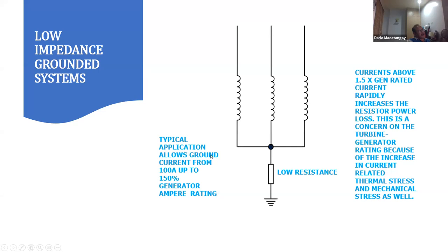What they do is sometimes they will design the ground current to be about 100 amps to about 150% of the generator ampere rating. So you allow 100 amperes to 150%, and size the resistor based on this generator ampere rating. You limit the resistance to allow 100 amps to about 150% of the generator ampere rating.